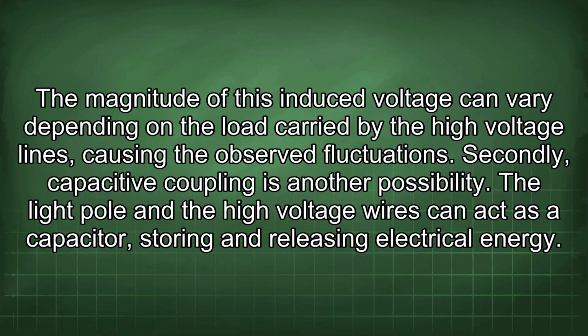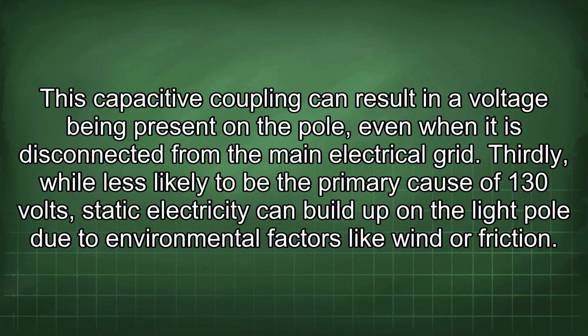Secondly, capacitive coupling is another possibility. The light pole and the high voltage wires can act as a capacitor, storing and releasing electrical energy. This capacitive coupling can result in a voltage being present on the pole, even when it is disconnected from the main electrical grid.